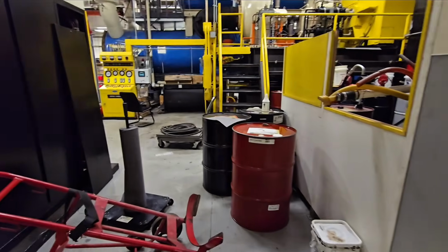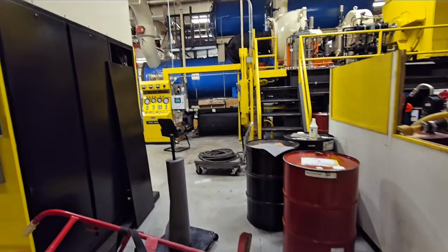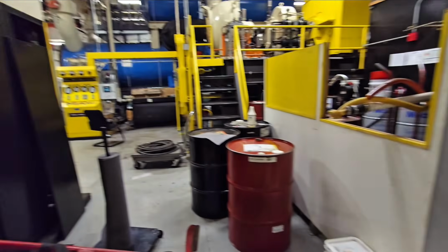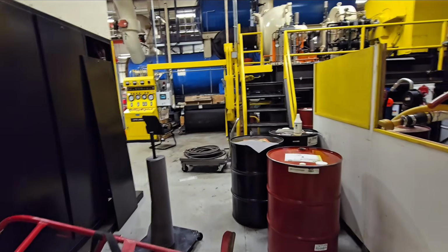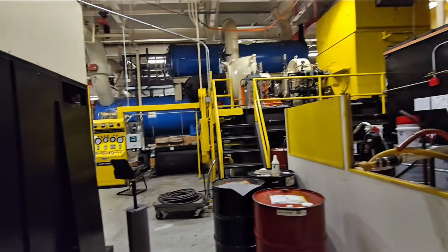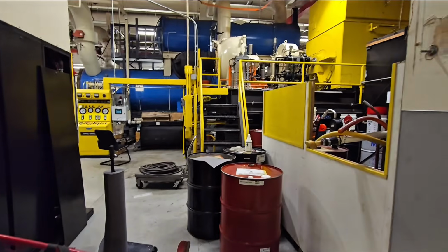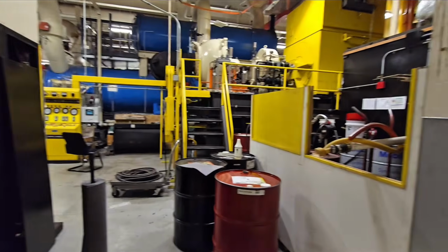How many amps do these draw? Because I assume with such a high voltage... The full load amps of that machine is 180, so 180 amps at 11,500 volts. You do the math on that to get the wattage — it's pretty high.